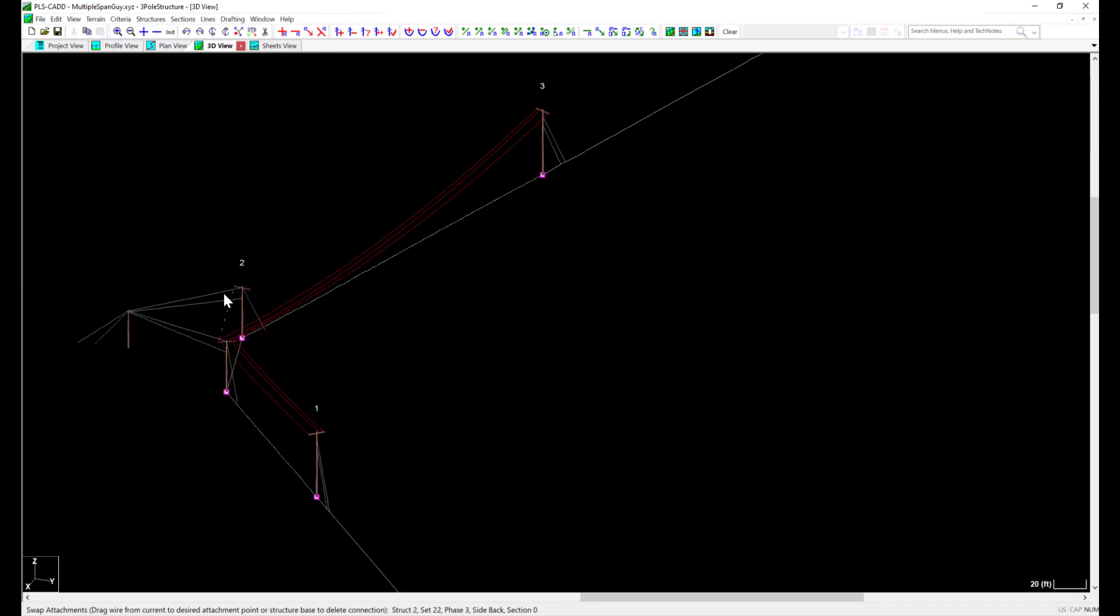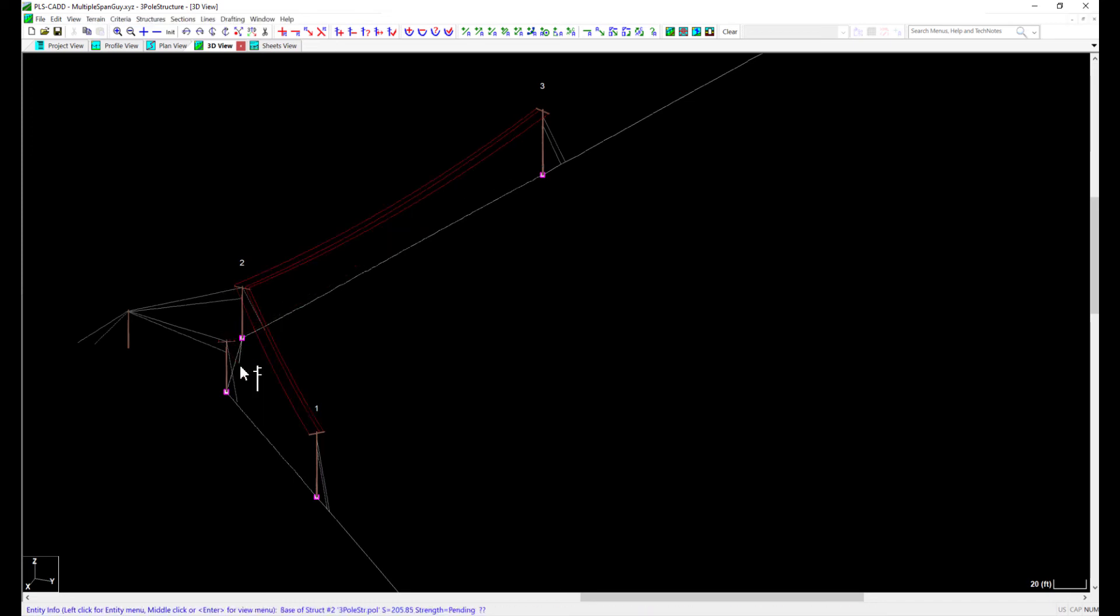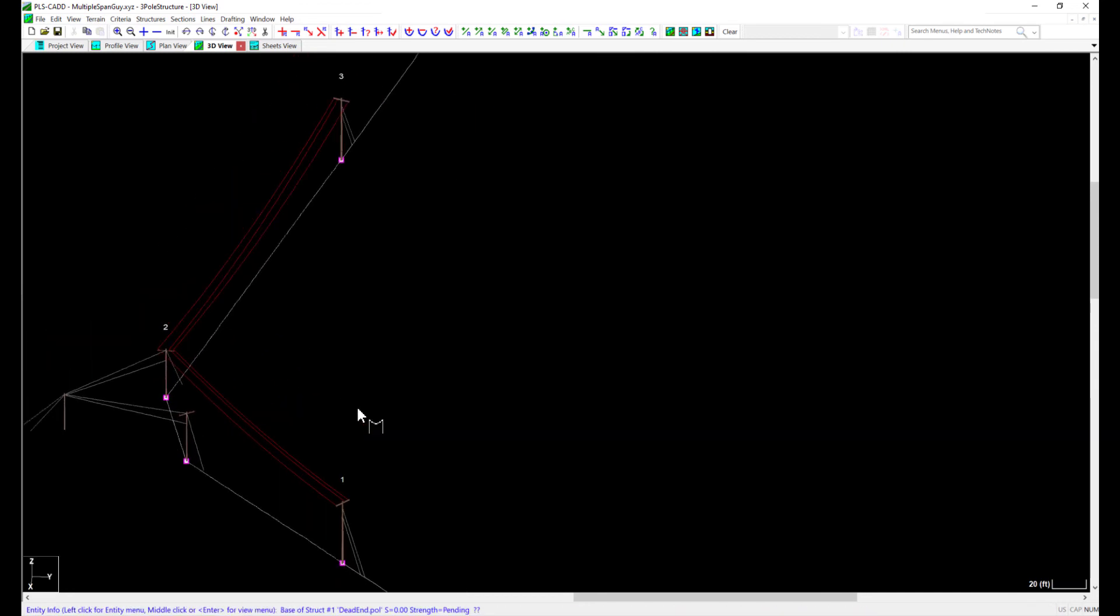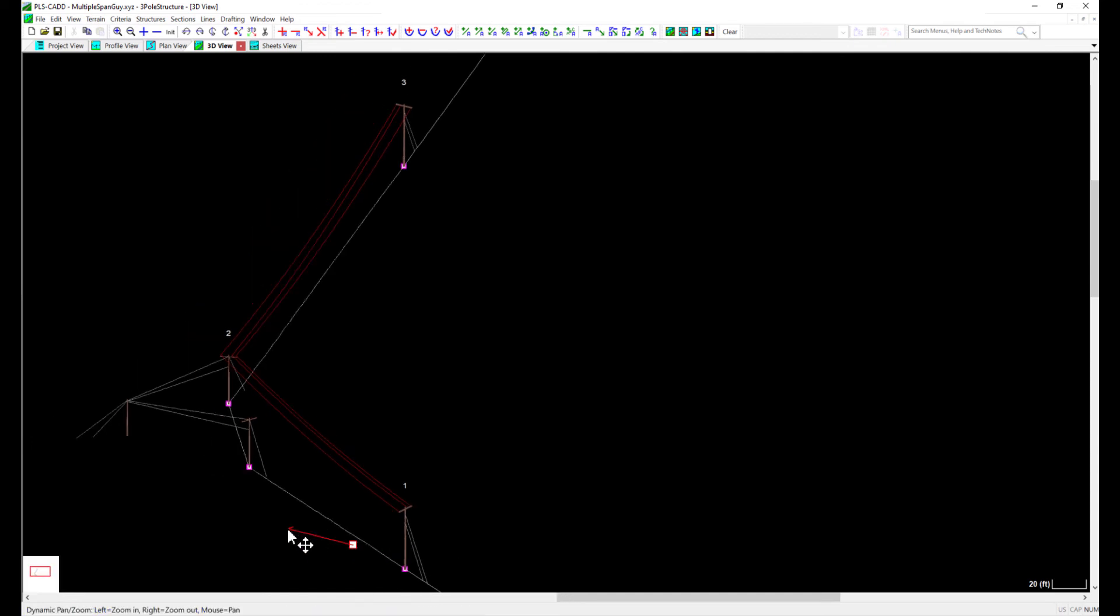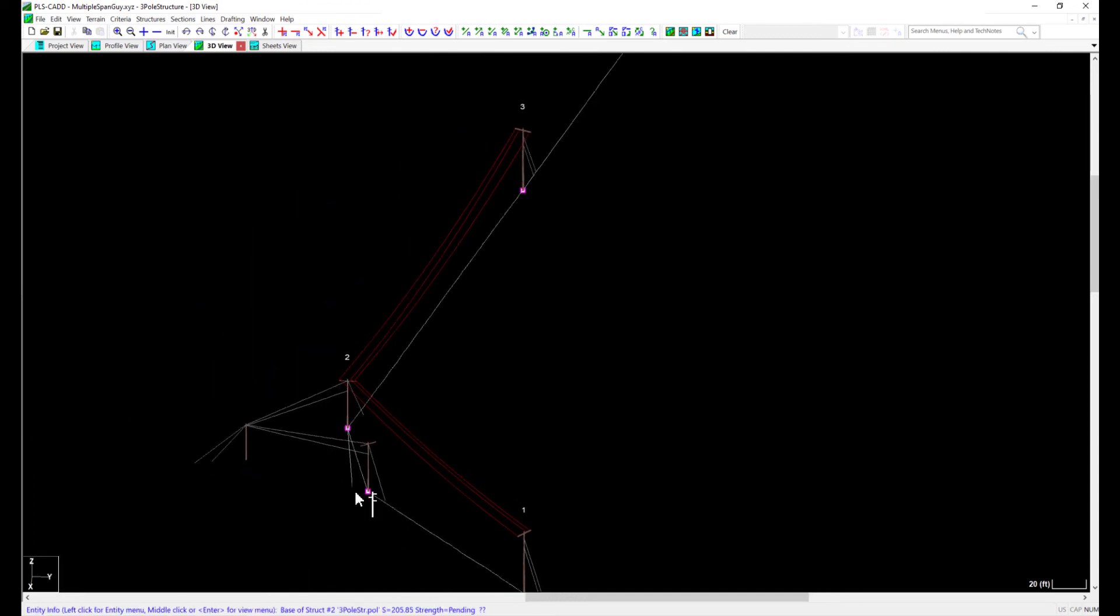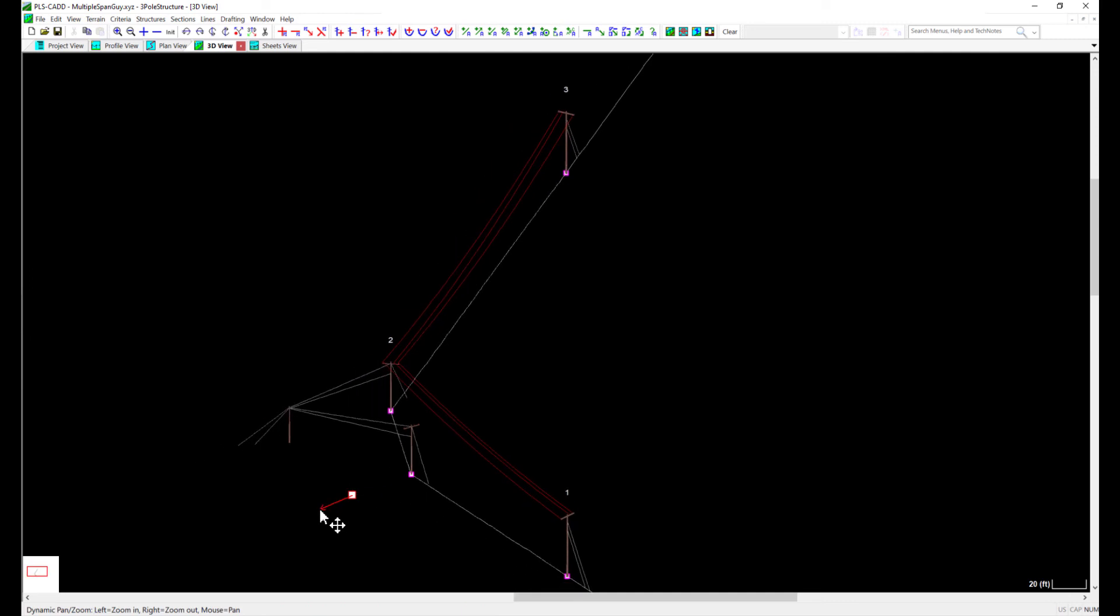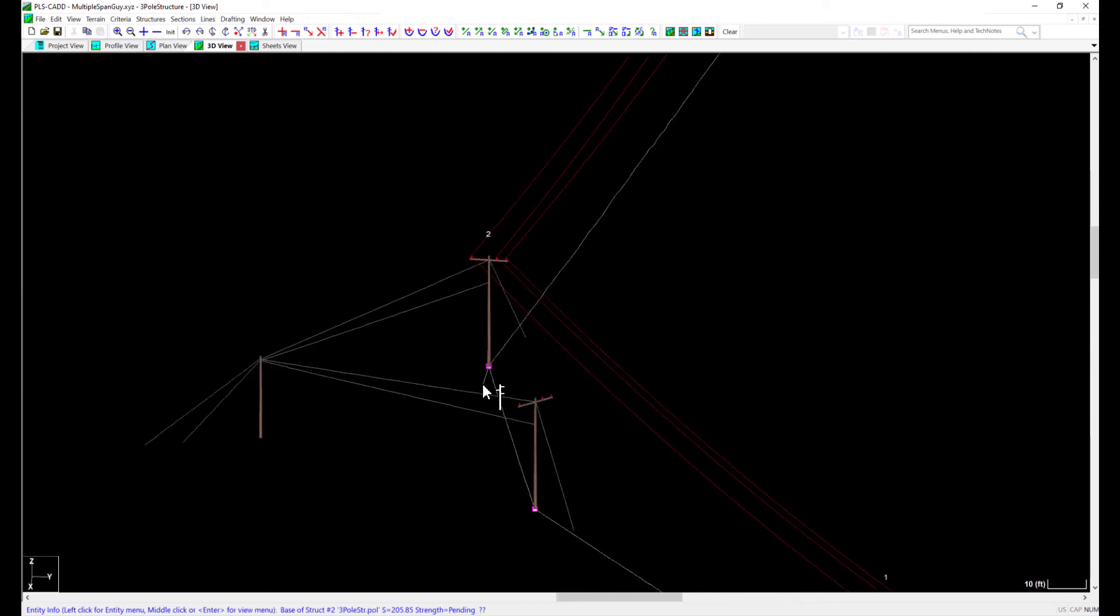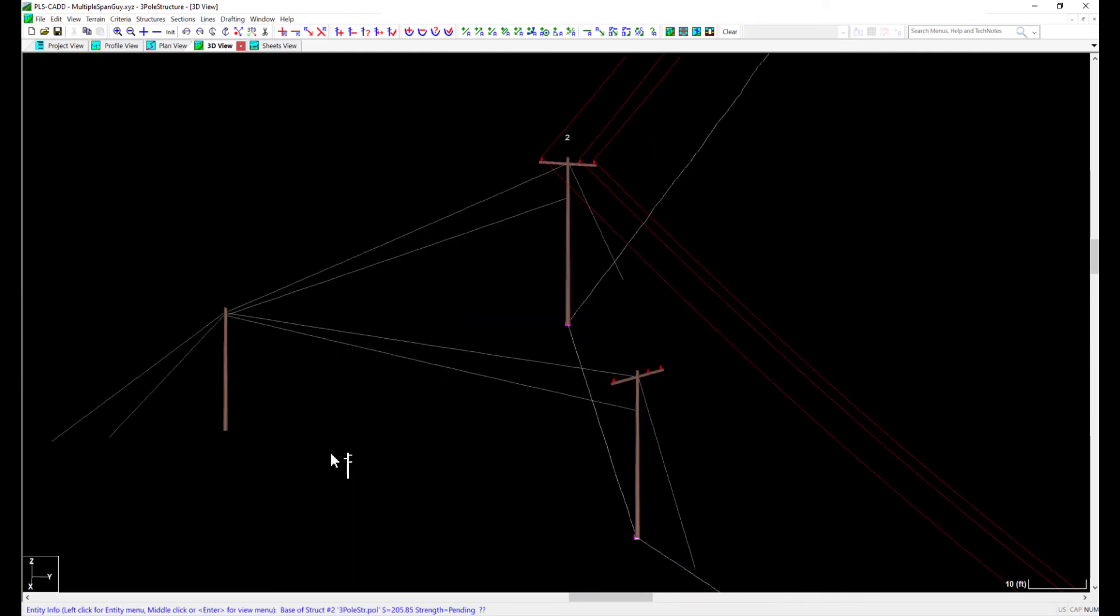The reason for this is because PLS-CADD only allows me to string a conductor to a structure once. We can string a head and back spans to a structure when using dead-end sets, but we cannot string to two tangent sets or between two dead-end sets on the same structure. Now we are left with the dilemma of how to string wire to both of these structures and have the program perform the analysis correctly.